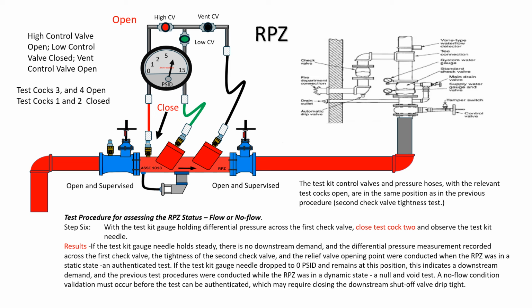An authenticated test. If the test kit gauge needle dropped to 0 psid and remains at this position, this indicates a downstream demand, and the previous test procedures were conducted while the RPZ was in a dynamic state. A null and void test. A no-flow condition validation must occur before the test can be authenticated, which may require closing the downstream shutoff valve drip tight. Note: a decrease in inlet pressure causes a change in the PSID, which may temporarily drop the gauge reading to 0 psid. If this occurs, marginally break the connection at test cock 3 to restore the first check valve differential. Once the differential pressure is restored, tighten the low pressure hose to test cock 3, and observe the test kit gauge as stated.